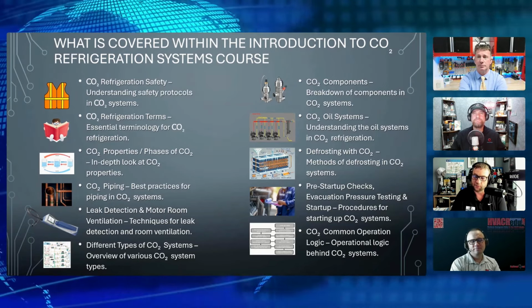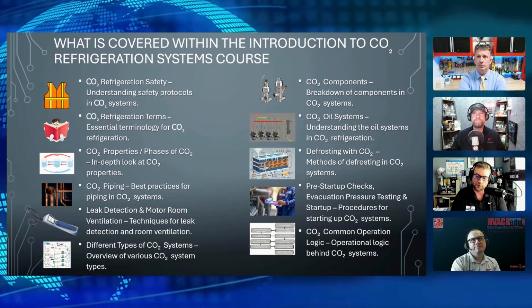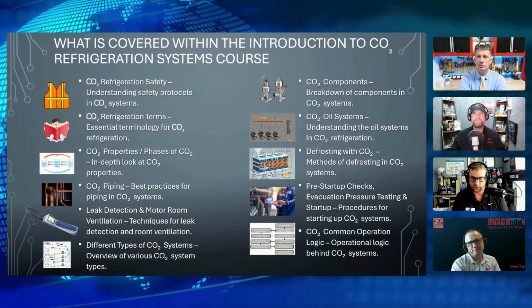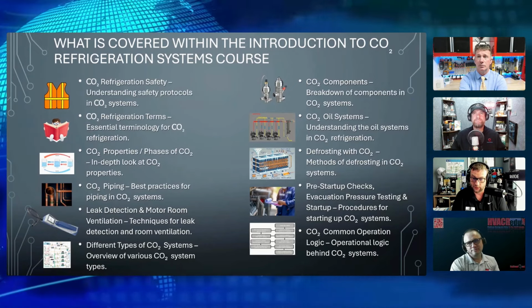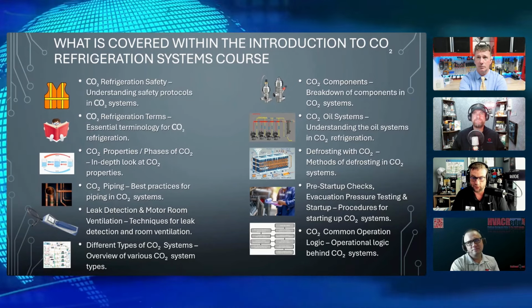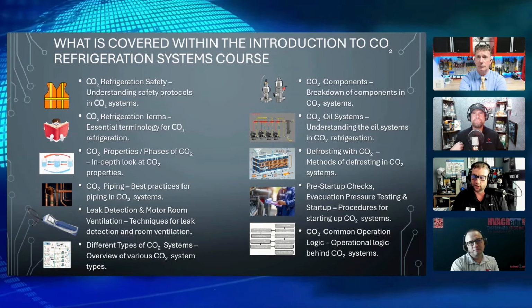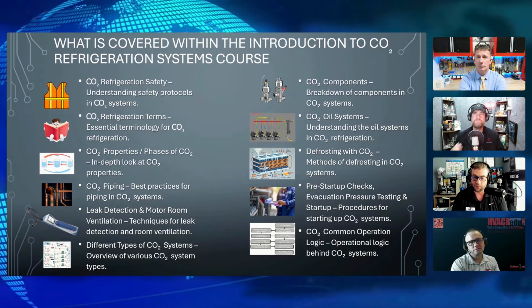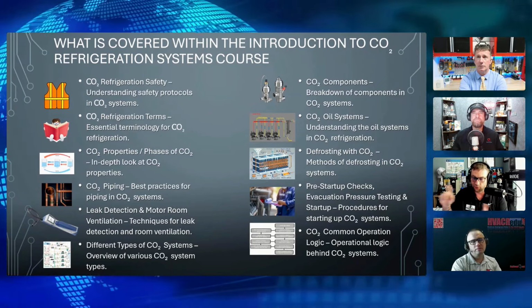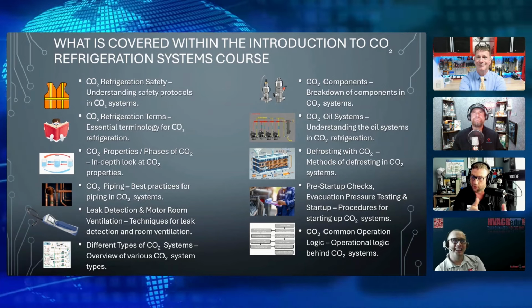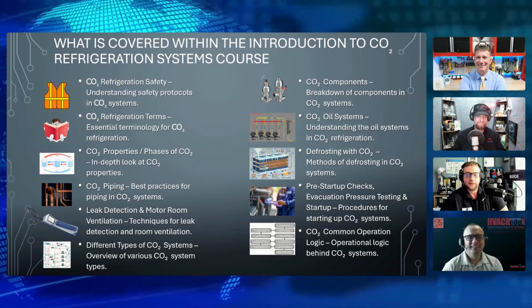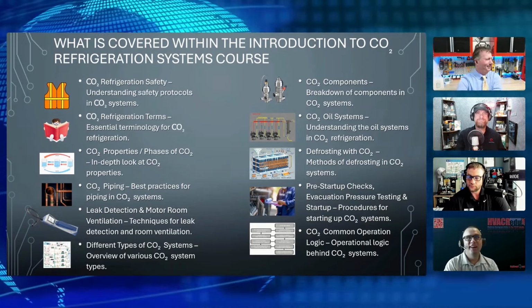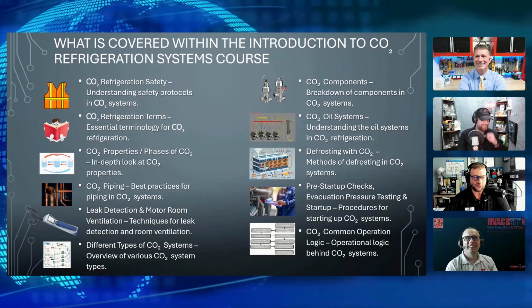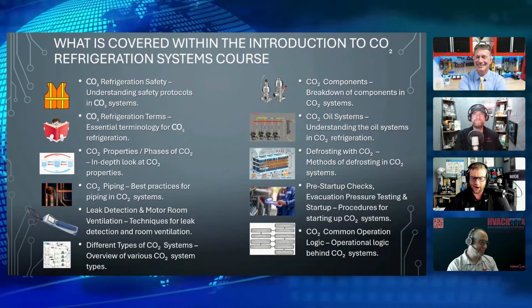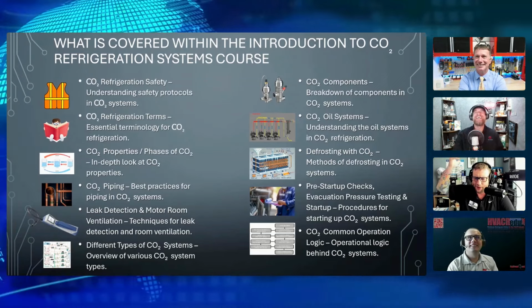So now you have to segregate and isolate parts of the system in order to leak check, as far as pressurizing the system, so we don't overpressure. If I just send it off and put 1,500 pounds in there, I'm going to have five different reliefs blowing and never get to the point where I need to be, right? Where's this gas going? Someone said to me, we're back in the days of R12. We just let it fly. Let it go.